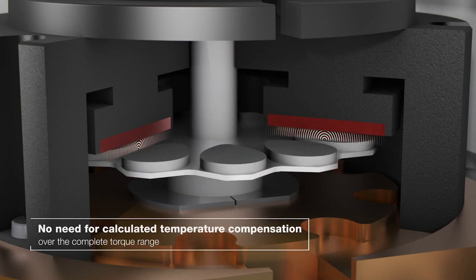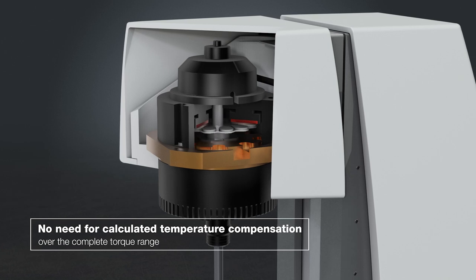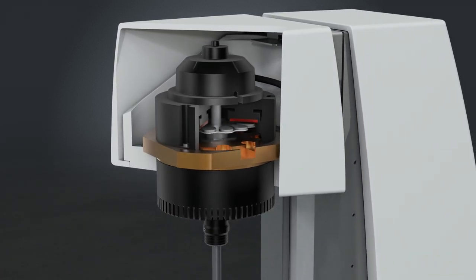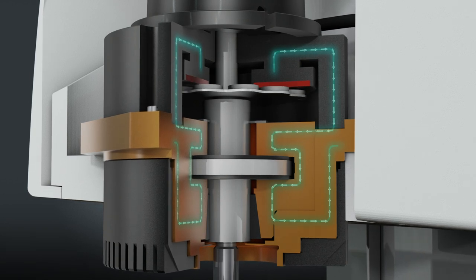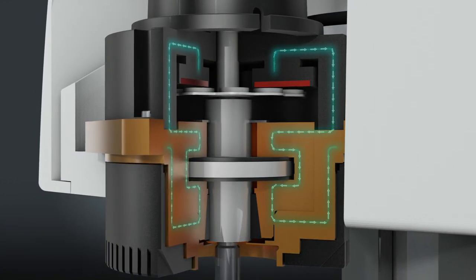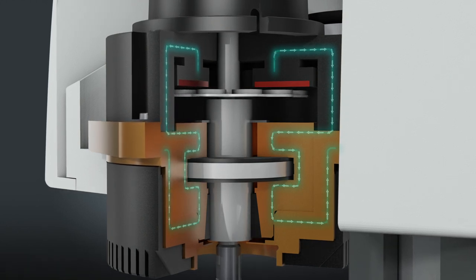The motor's design ensures avoidance of eddy currents, which would cause heating problems and signal drifts. Additionally, the active thermal management of the motor ensures stable results even for long-term measurements at the highest torques.